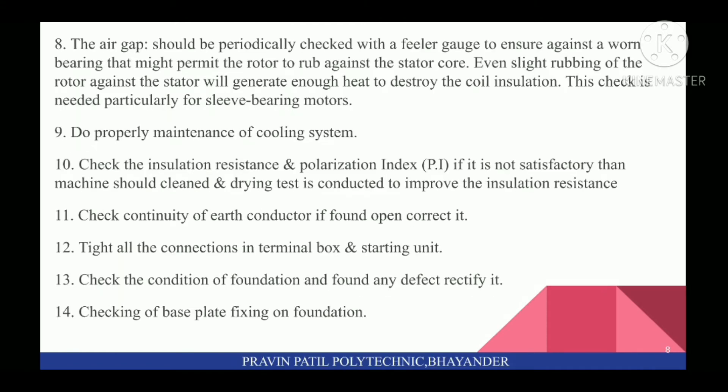Next, air gap should be periodically checked with a feeler gauge to ensure against a worn bearing that might permit the rotor to rub against the stator core. Even slight rubbing of the rotor against the stator will generate enough heat to destroy the coil insulation. This check is needed particularly for sleeve bearing motors.